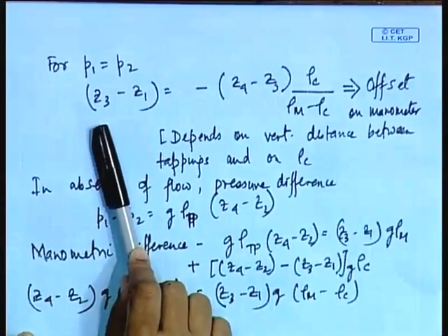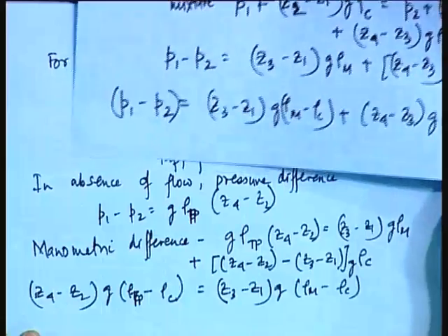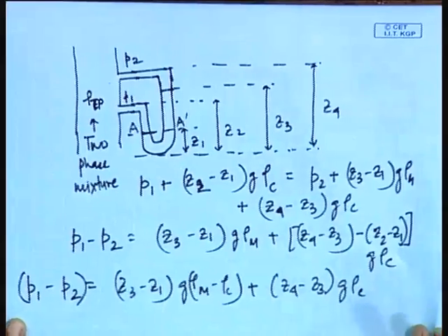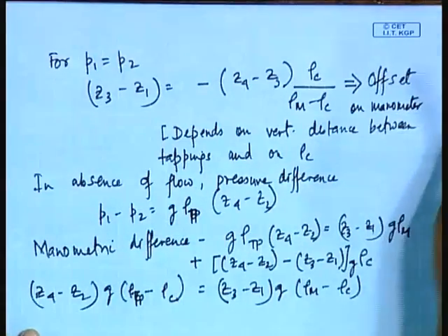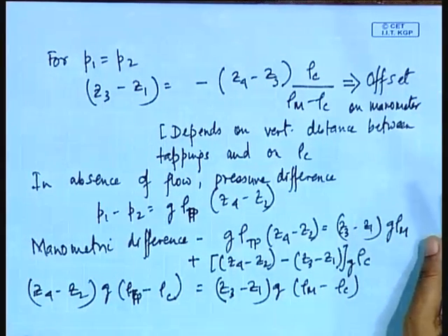Number two, since in that particular case rho c will be much less, we can get more accurate predictions of pressure drop if rho c is less. So pressure drop measurements can be more accurate and the offset is less for gas filled lines. But the pumping action is so very high and the tendency of liquid entering into gas filled lines is so drastic that for most of the cases we do not prefer gas filled lines. We prefer liquid filled lines unless some very special circumstances or applications force us to adopt gas filled lines, correct?